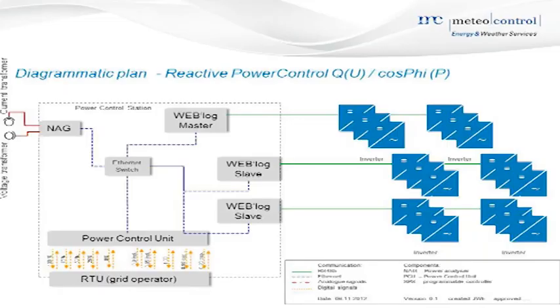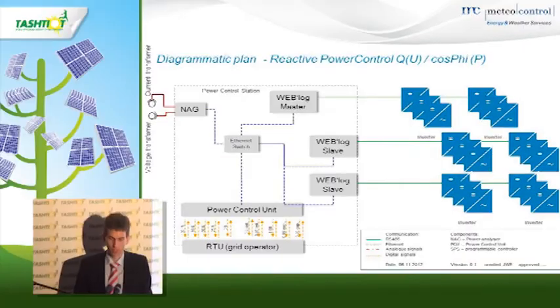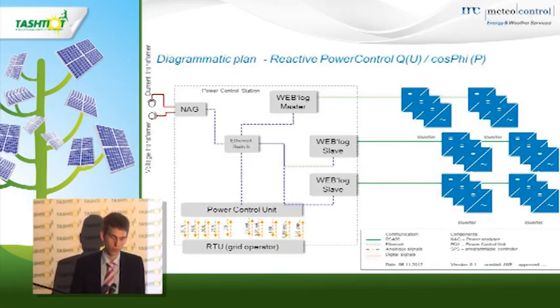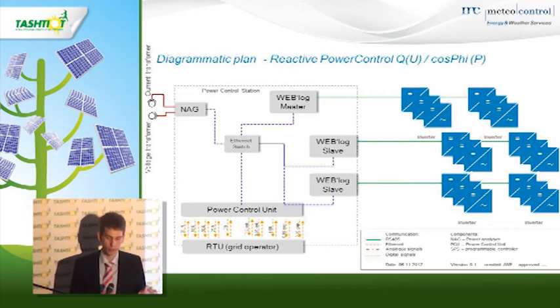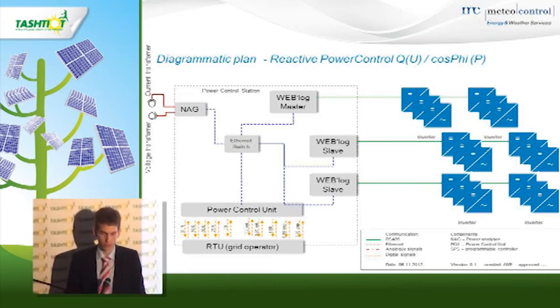So this would be an example, a schematic of a real plant. So you see again the power quality analyzer connected to voltage and current transformers. The whole plant control system is connected over Ethernet. And you have to define one data logger as master, taking care of the control and sending the set points to all the slaves in the system.